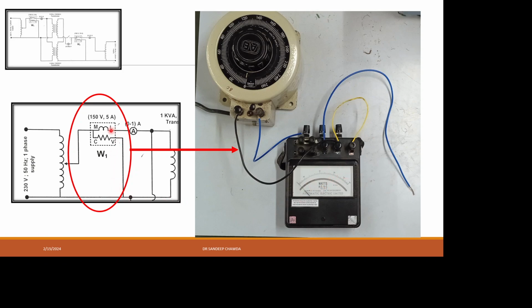So what you have to do is connect a wire from L, which will then be connected further. We have taken a blue wire and connected it to L, and now it is left open because we are going to connect it to another instrument. Then we can see here is a C terminal, the common terminal, and M and C are connected together in this circuit diagram. There is no internal connection between M and C, so we have to take another wire and short M and C. Here the yellow wire is taken, one end connected to M and the other end to the common terminal, so it is basically short circuiting.